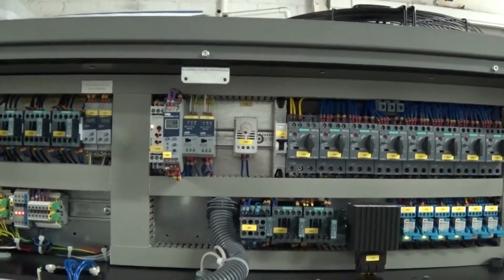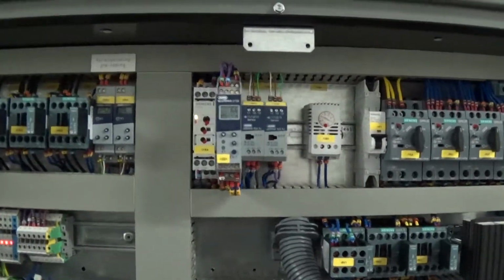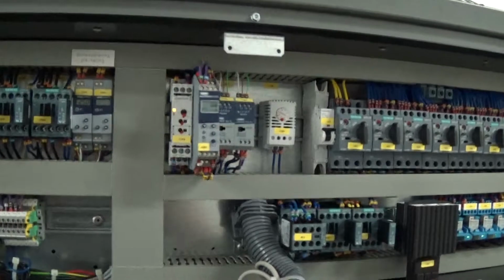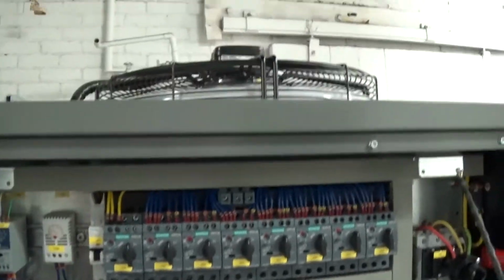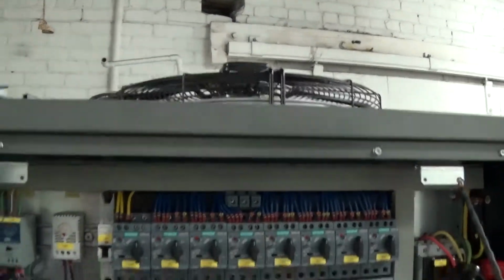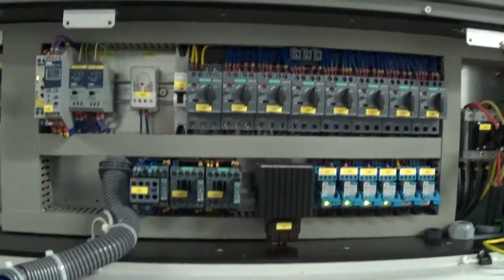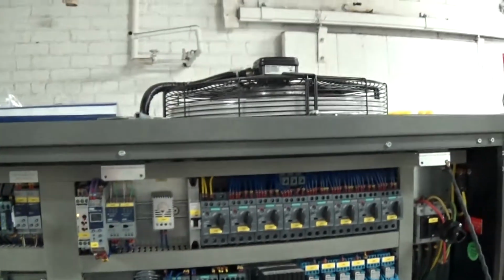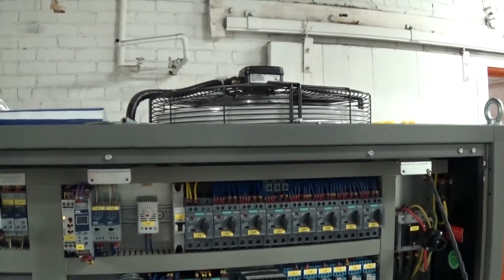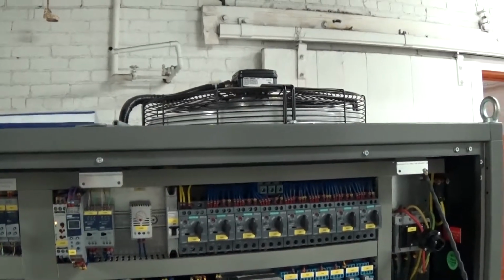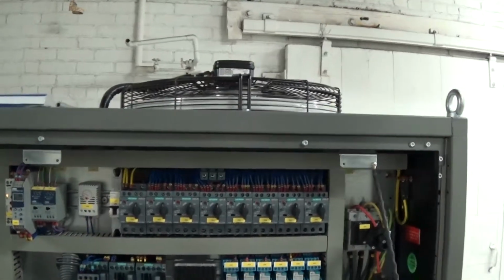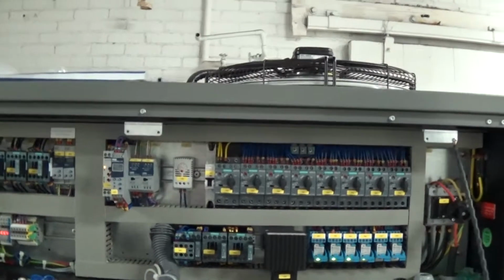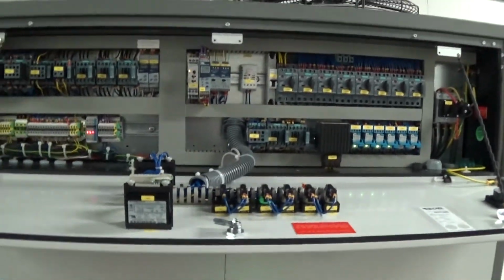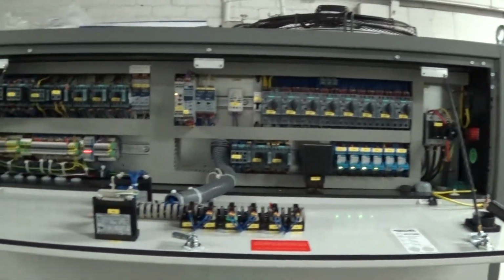And I think I just heard one compressor kick on, then a second already, and the fan comes on separately, not necessarily at the same time. In some real simple chillers, whenever the compressor is on, the condenser fan is on. That's not the case here because we're basing it off of pressure. It's not tied in exactly with the electrical of the compressor.